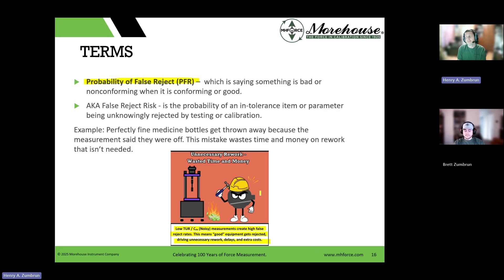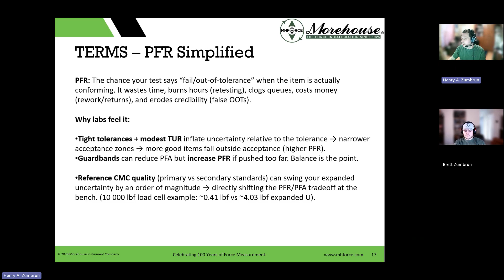But simplified, it's the chance you say something fails when it's actually conforming. Why the labs feel it: tighter tolerance plus moderate test uncertainty ratio inflate uncertainty relative to the tolerance, narrowing acceptance zones. These are things that happen. But the highlight is reference CMC quality. Primary versus secondary standards can swing your expanded uncertainty, so they're going to set your guard bands. I'm just going to move right on to that when we talk about it.